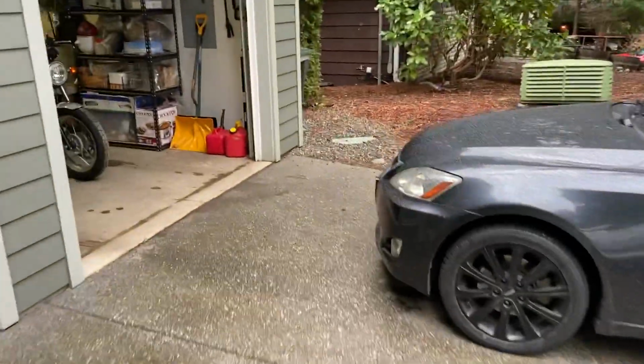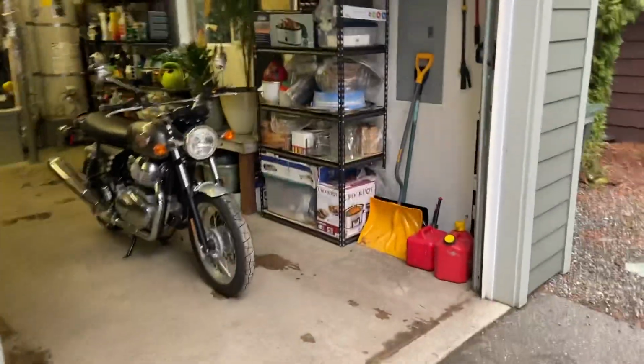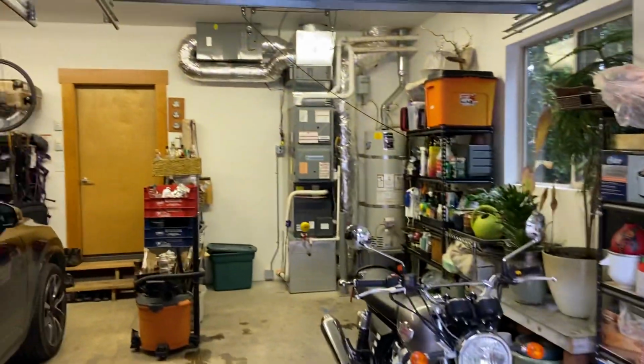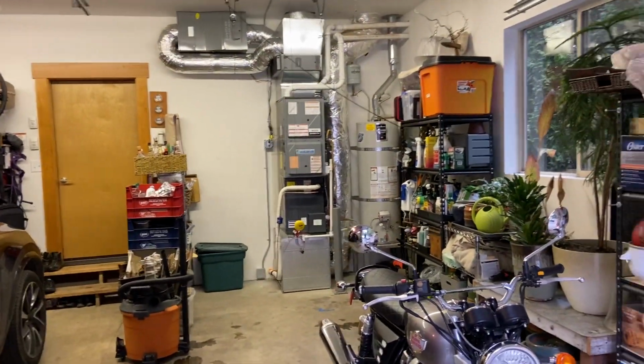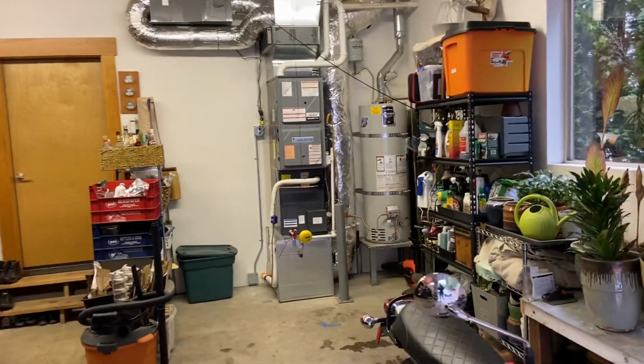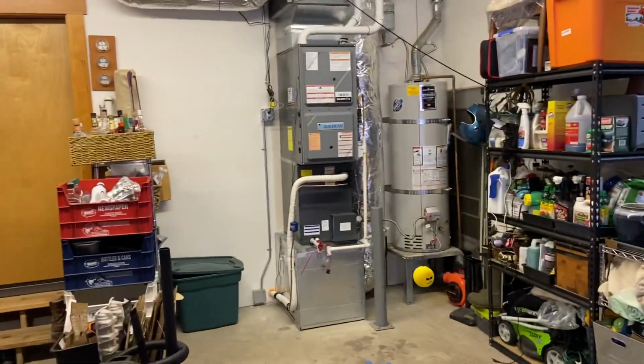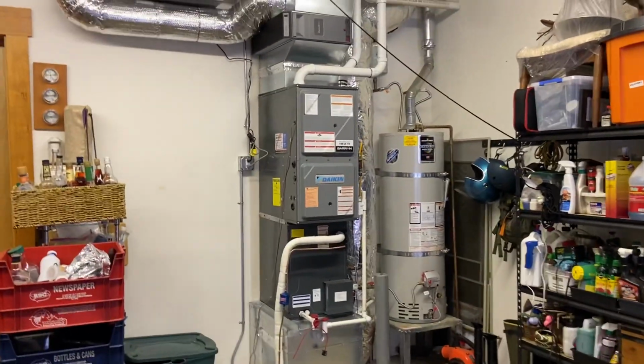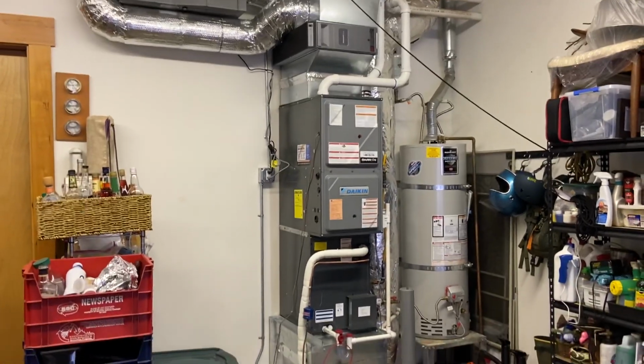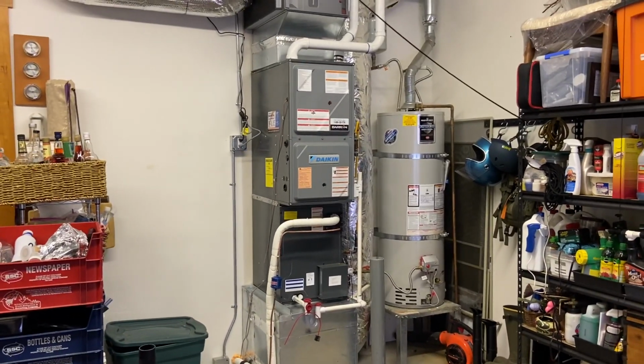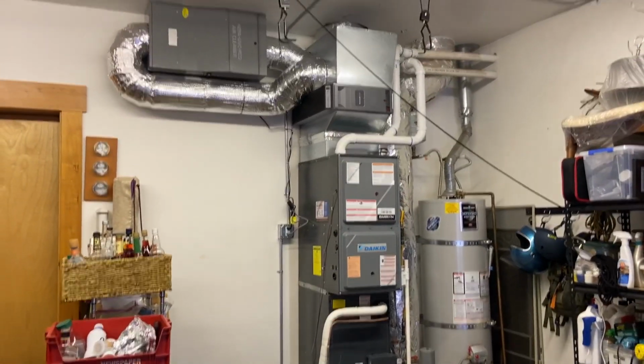So we cleaned and sealed the ductwork. One of the things that was really important here, and a kind of distinguishing factor, was that the ductwork had gaps everywhere. The best way to fix that was Aeroseal, in a 2-story house, getting up through the walls and everything. But here's the Daikin setup.